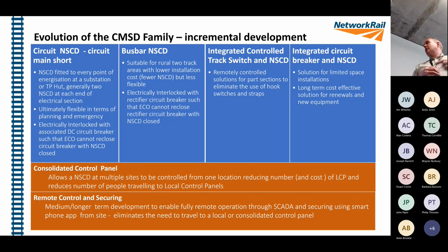As we started this journey, we had a standard negative short circuit device. As we progressed, we've now got busbar short circuit devices, meaning we only need to fit one device rather than 4 on a 2-track railway. We don't have to fit those at TP huts, which can make it cheaper to fit to more rural outer areas like Bournemouth, Weymouth, and the Portsmouth line, because it fits into that possession strategy with busbar type technology. We've now got an integrated control track switch and short circuit device in one box. So when we fit a CTS now, we don't have to fit one device and then an NSCD either side of it. It all comes as one integrated package, which makes it cheaper to install.